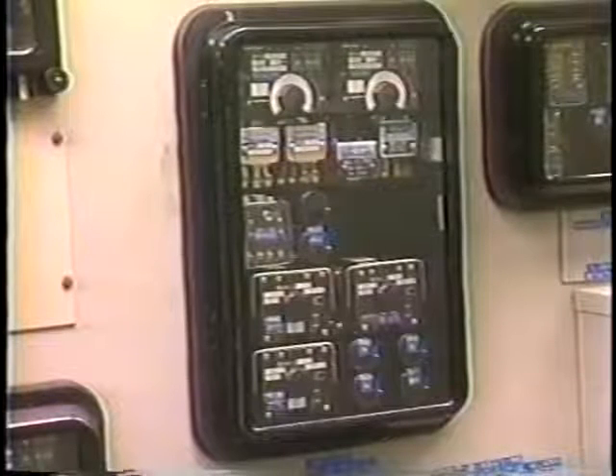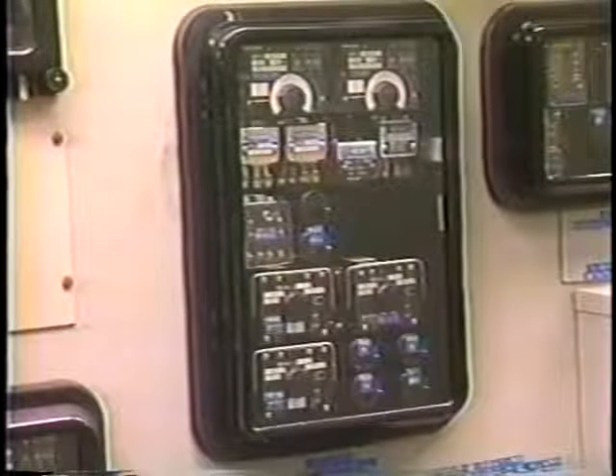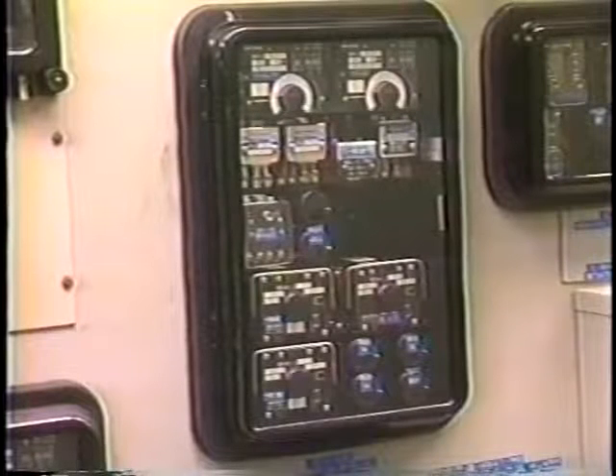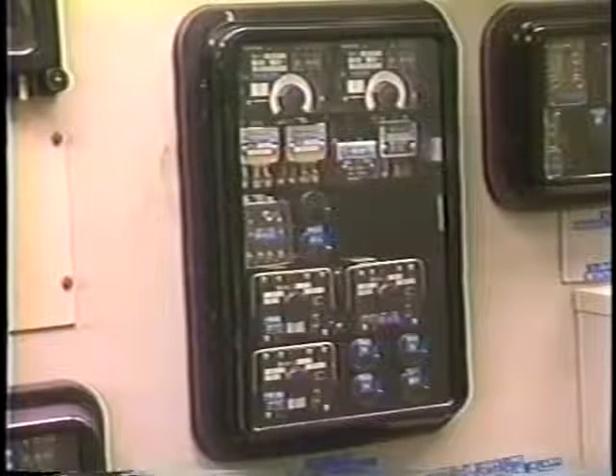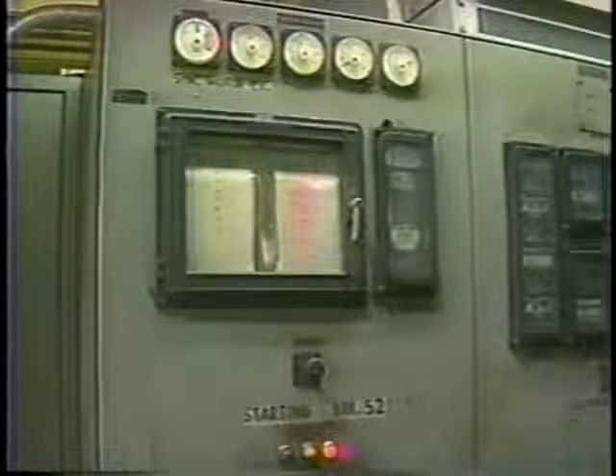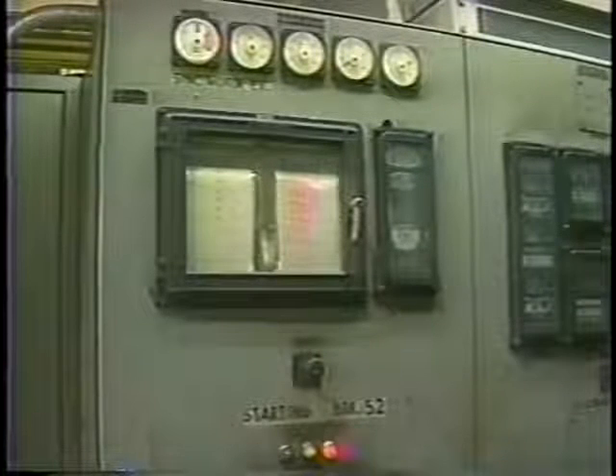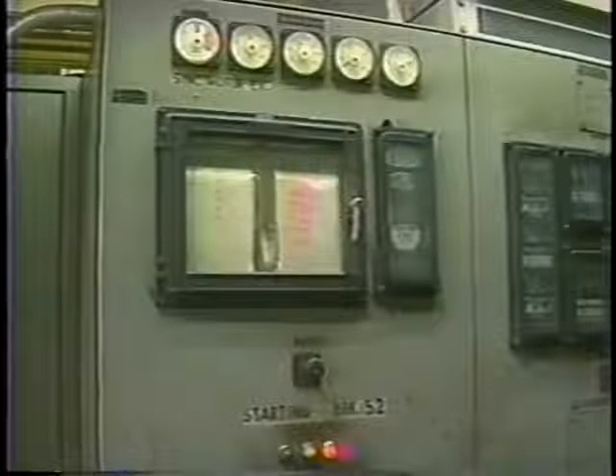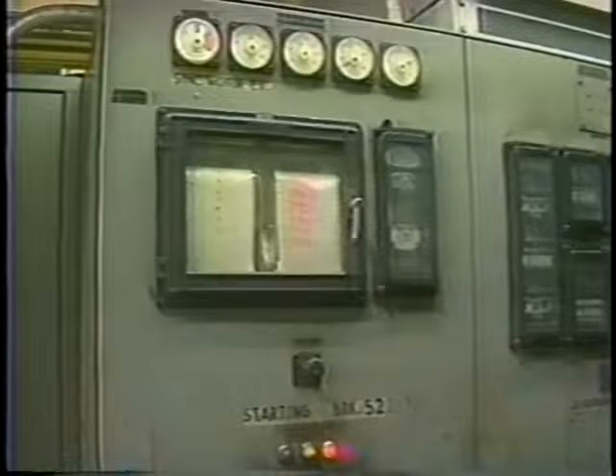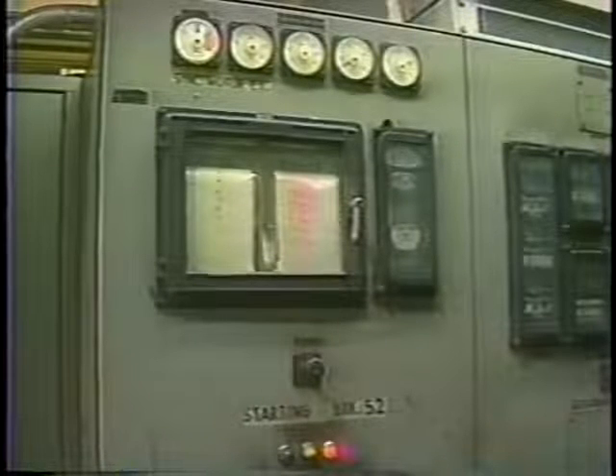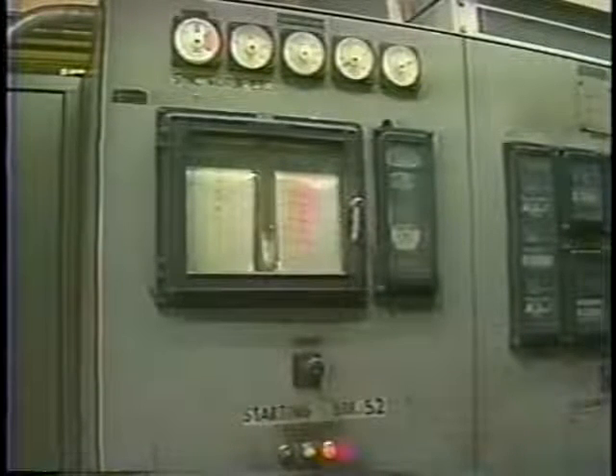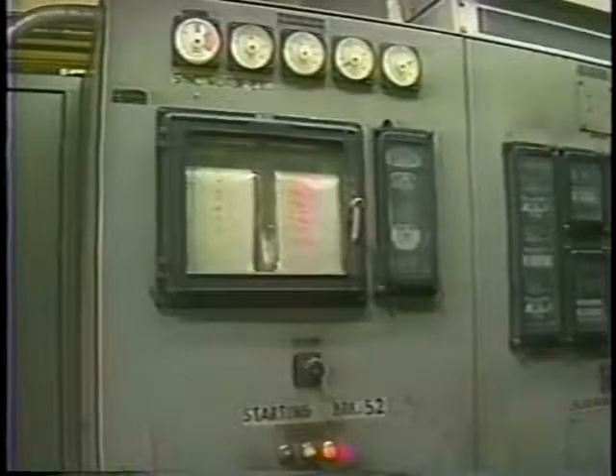You will remember in an earlier tape that we discussed special protection required for the generator during startup. Startup protection for the synchronous motor is similar. It's usually provided by the motor manufacturer and includes protection for starting, switching in the field, and synchronizing. Okay, so much for synchronous motors.